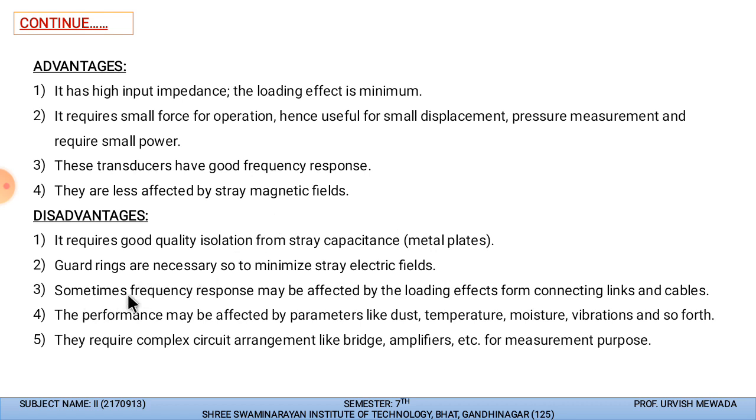Sometimes the frequency response may be affected by the loading effect from the connecting links and the cables. We need to keep this point in mind while we use such a device for pressure measurement, and protect it from other loading effects, like from the cables and links. Also, the performance may be affected by parameters like dust. This is a major point to keep in mind while using such a device for pressure measurement. Dust can affect the performance of the diaphragm, so we need to protect the gauge from the dust. Then temperature and moisture can also affect the diaphragm material.